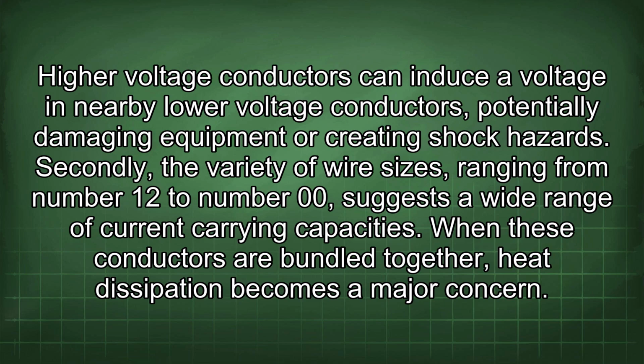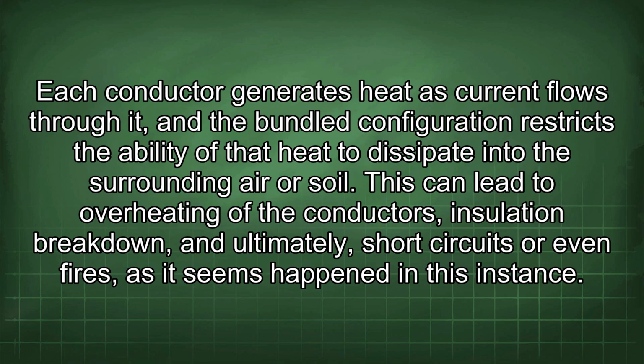Secondly, the variety of wire sizes, ranging from number 12 to number 00, suggests a wide range of current carrying capacities. When these conductors are bundled together, heat dissipation becomes a major concern. Each conductor generates heat as current flows through it, and the bundled configuration restricts the ability of that heat to dissipate into the surrounding air or soil.